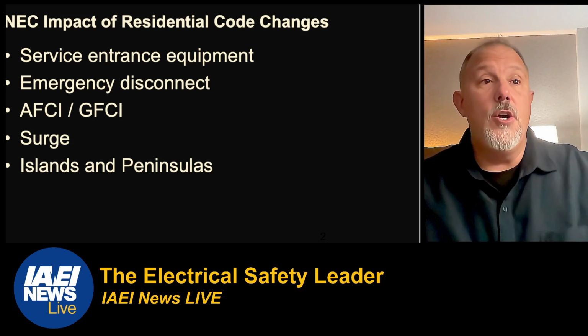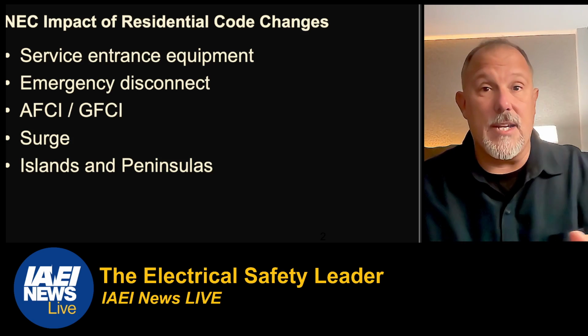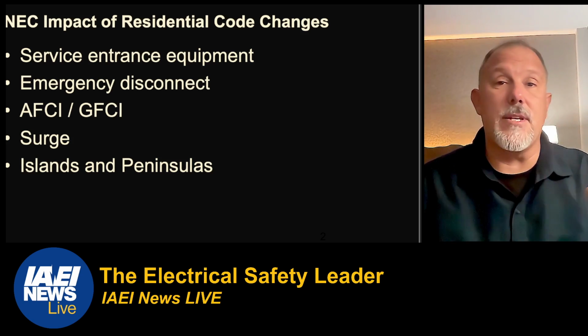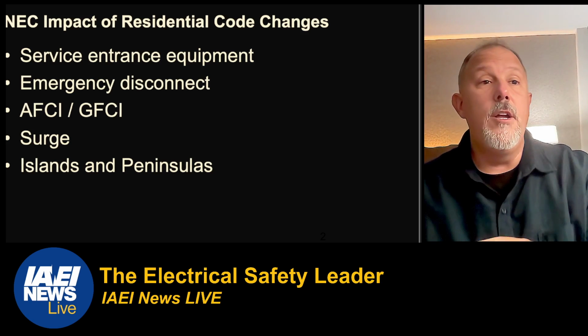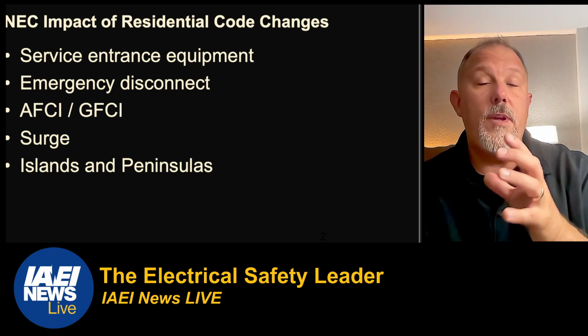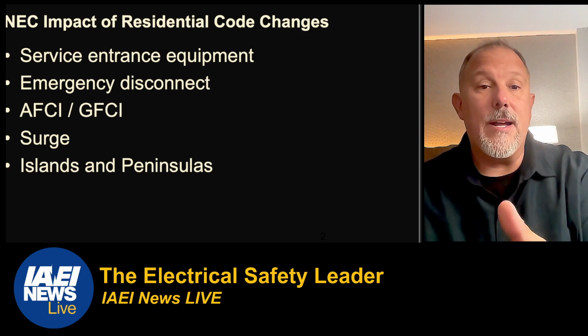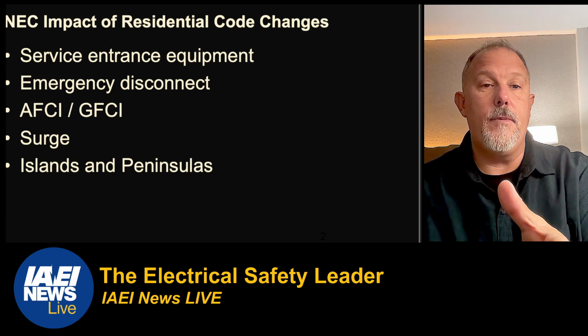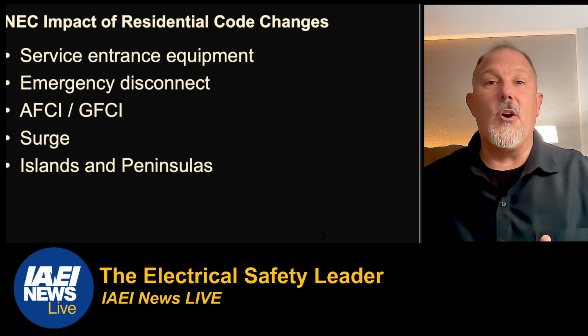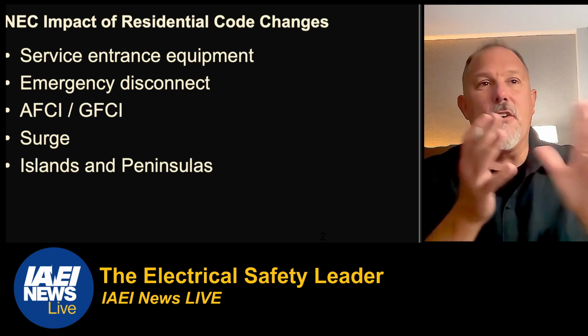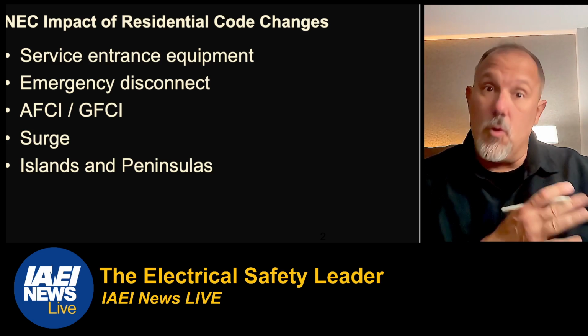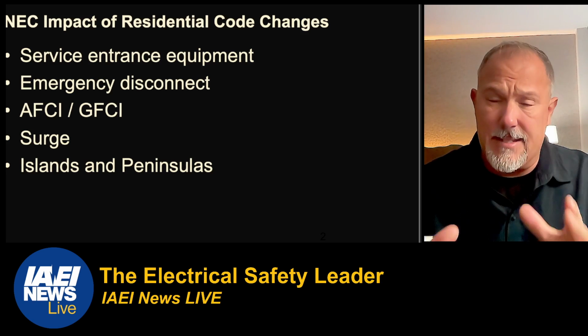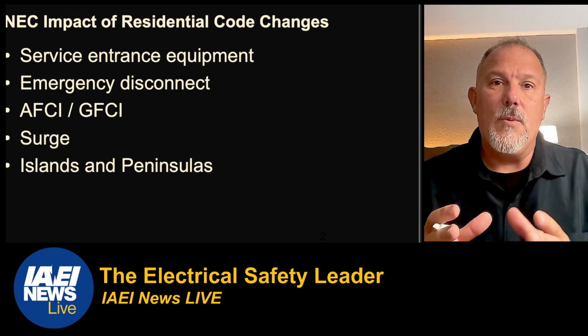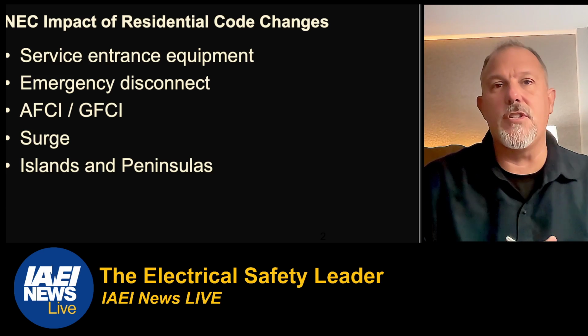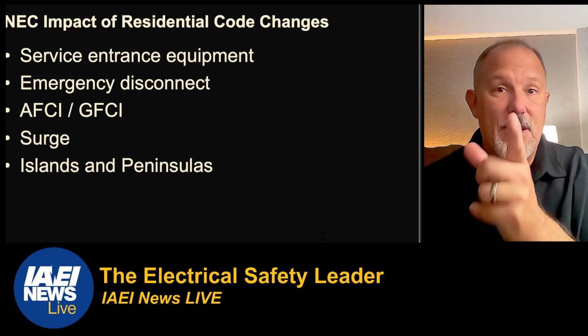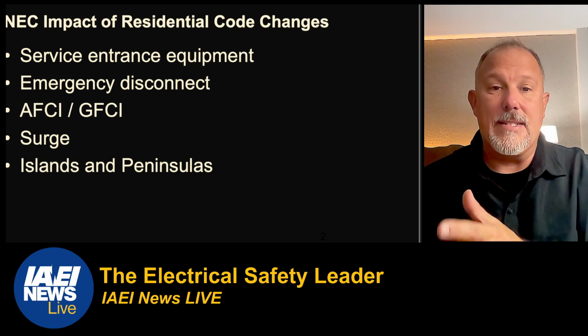The emergency disconnect we saw over the last two cycles, and I say three, meaning the 2023 code cycle. So for at least three cycles now, we have seen changes that directly try to address first responders. If you recall, the first round, which failed on the floor of the annual meeting, I think they called the firefighters disconnect. I know we had some debates around that and those requirements. It failed the first time around, it passed the second time around, and as you're going to see, it's starting to expand its application.